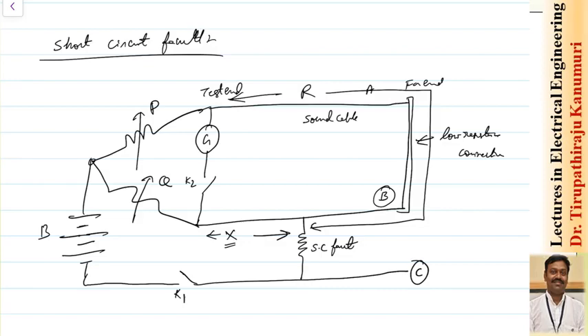You might wonder how to know which two cables to connect and which one is the sound cable. I already discussed in the last class — using the megger, I can identify which cable has a fault and which does not. Once you know there is a fault, this method is used for detecting the location of the fault. If the fault is between conductors B and C, I can employ this method. If all conductors are faulty, then you can use this method only if one more cable running parallel — which is a sound cable — is available.